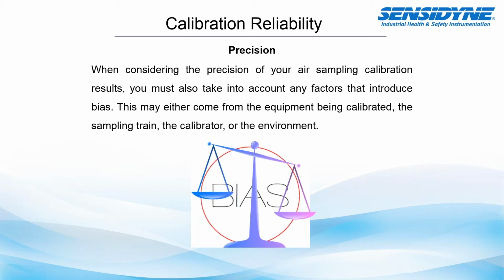Now, precision as opposed to accuracy. When you consider precision of your sampling calibration results, you must also take into account any factors that introduce bias, and I'll explain how that bias comes into play. It may come in from either the equipment being calibrated, the sampling train itself, the calibrator, or even the environment that you are calibrating in.